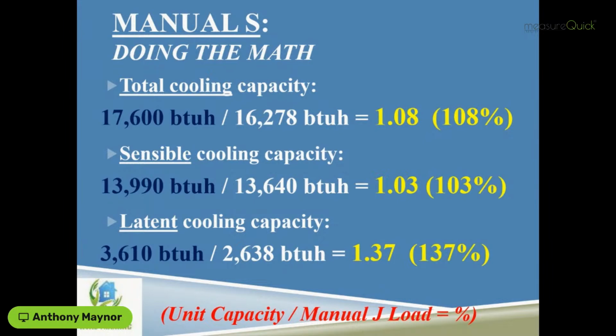You've got to make sure that your system has the capacity to maintain that design relative humidity in that home. You've got to make sure without any hesitation that your system will meet at least 100% of that design cooling load. It's okay to have some excess there, but we don't want to come up short. If we come up short, we really need to go back to the drawing board and look at different sizes of equipment to see if we can get something that still matches up for our cooling oversizing factor, but provides us that 100% or greater on the latent cooling side.